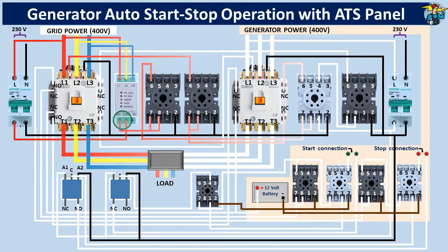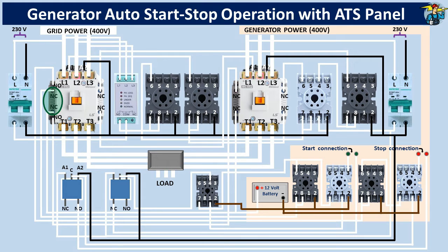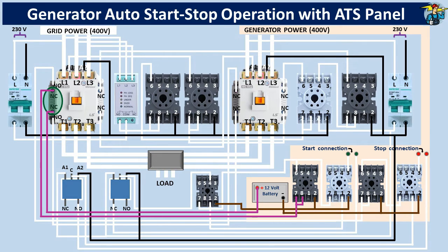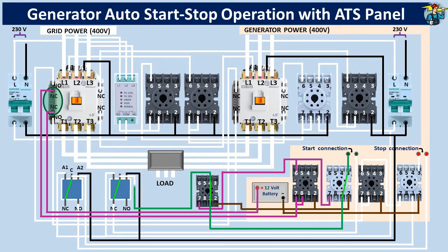When the main power supply fails, the normally open auxiliary contact points on the mains contactor will close. This allows power from the 12V battery to pass through to the generator start timer. A delay period of 2 to 3 seconds is set on this timer to stop unnecessary generator starting during momentary power cuts. After this delay period, the start relay and the start fail detection timer are energized. Terminals 1 and 3, normally open on the start relay, are now closed, but points 1 and 4 normally closed on the start fail timer still remain closed until the set delay time is reached. The common terminals of the 5-pin SPDT relays are connected to their normally closed terminals since they are not yet powered. The generator start push button points are now connected through the loop created through these 3 relays.